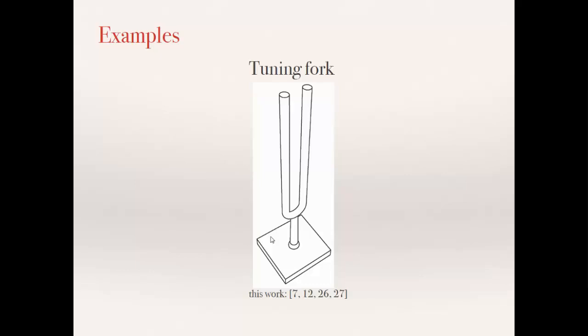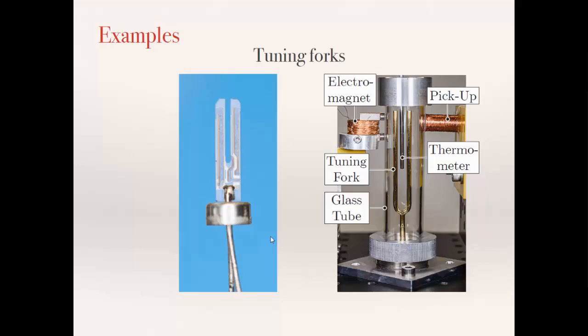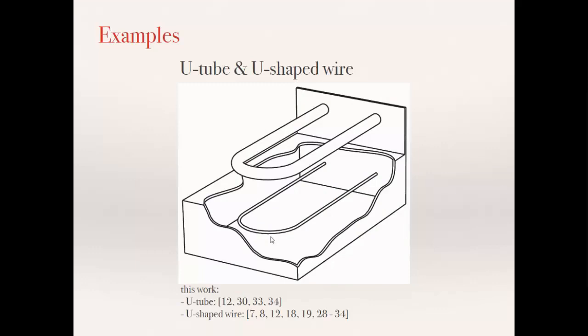I think the most promising devices for this viscosity mass density sensor are tuning fork-based sensors. There are multiple reasons for that. One of the main reasons is that their resonance frequency is the most stable by its mechanical structure. So they are singly clamped. They show low sensitivity to temperature. And they are balanced resonators, which is very important if you want to have handheld devices. Any other devices like singly clamped devices like micro-cantilevers, they depend on the surrounding of the clamping. So tuning forks. And yesterday I was also talking about U-tube and U-shaped wire resonance.